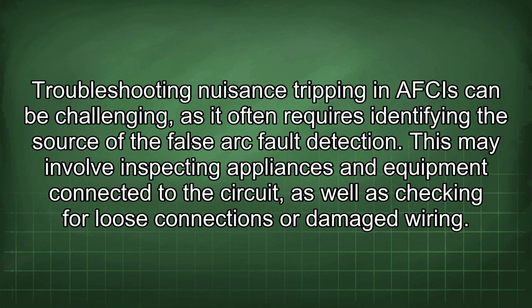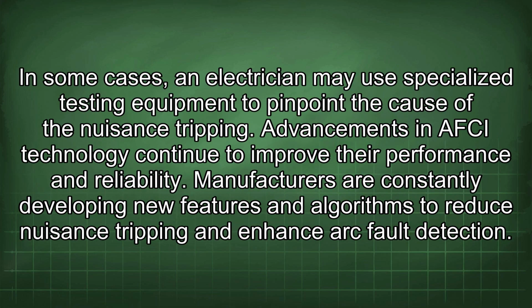Troubleshooting nuisance tripping in AFCIs can be challenging, as it often requires identifying the source of the false arc fault detection. This may involve inspecting appliances and equipment connected to the circuit, as well as checking for loose connections or damaged wiring. In some cases, an electrician may use specialized testing equipment to pinpoint the cause of the nuisance tripping.